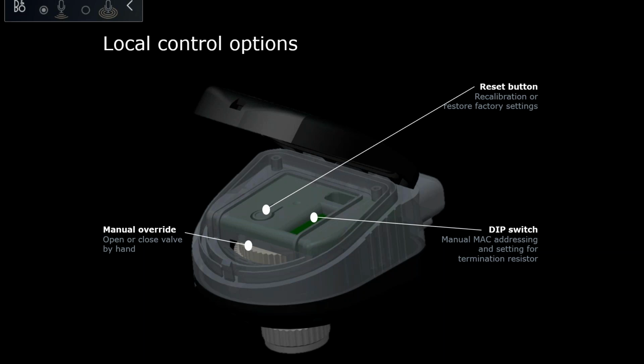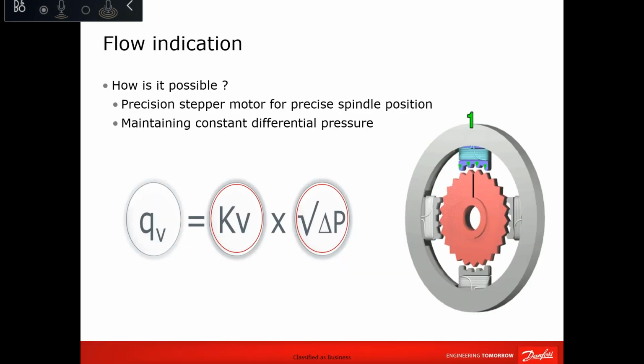The dip switch setting is used for manual MAC addressing, which is not required because the actuator automatically detects itself to the BMS. But it is also used to enable the 120 ohm resistance to end the loop. If you want to close a BACnet loop, you need to enable a 120 ohm resistance to make the BMS know that this is the last part of the loop. That is dip switch number 8. Dip switch number 8 is to enable the end of the loop. It is very important.